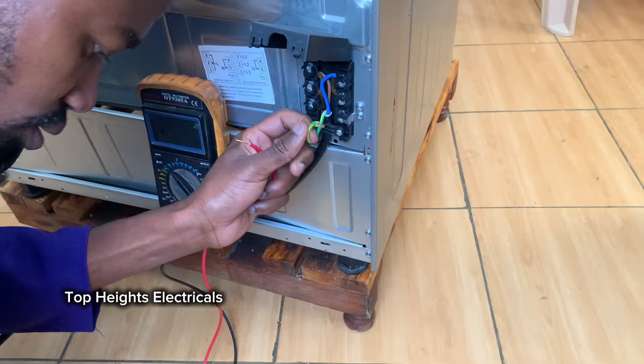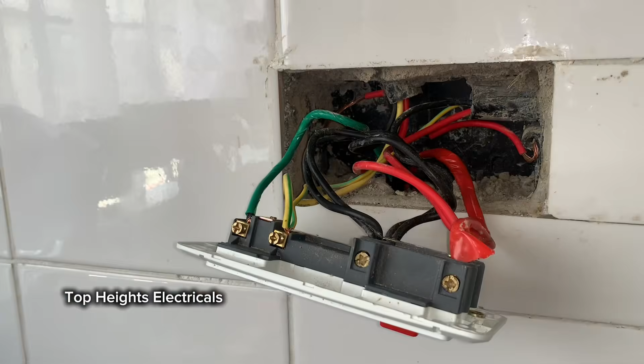We inspected the cooker and discovered that there were issues because the earthing connection was not properly done. The connection to the wire was done on the insulation. That could definitely compromise on the path of safety. So we had to sort that one out. But there were still so many problems in this home.